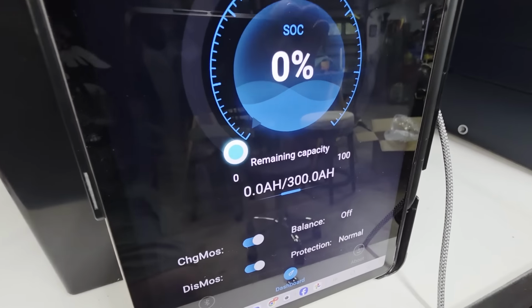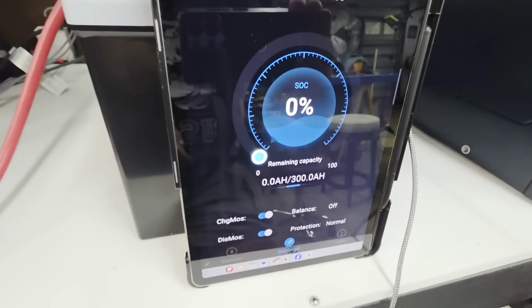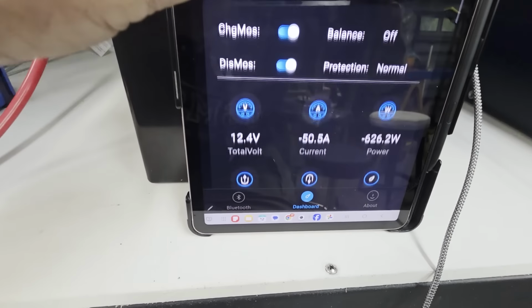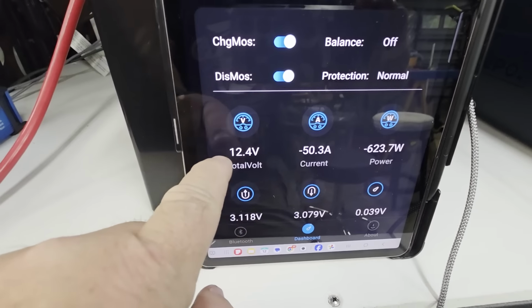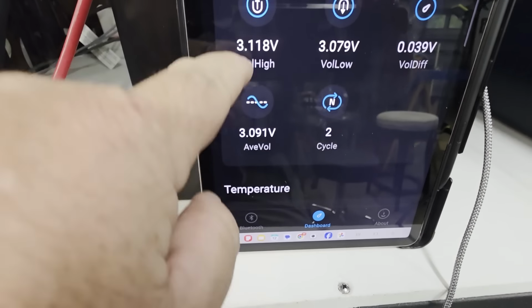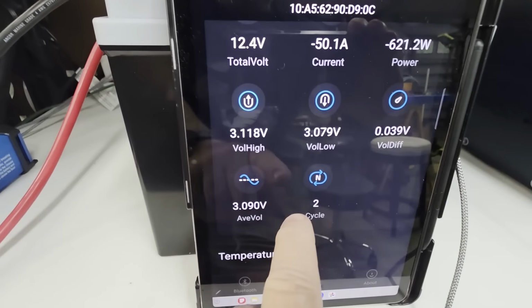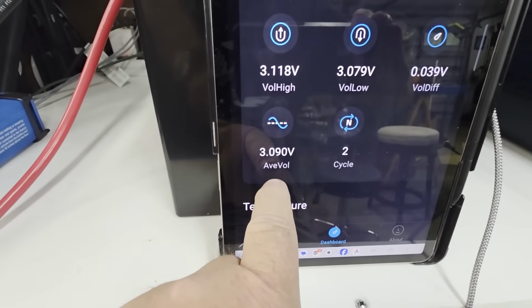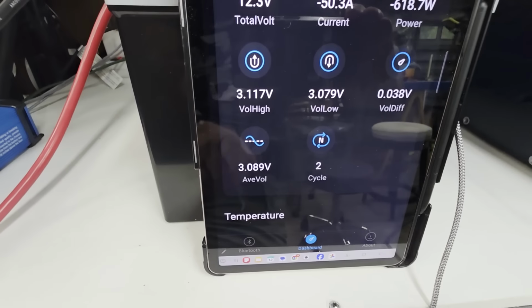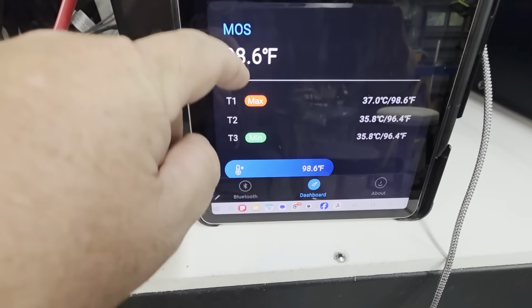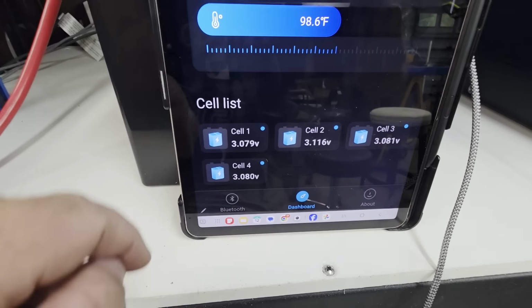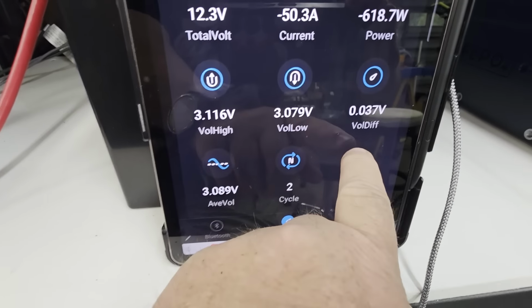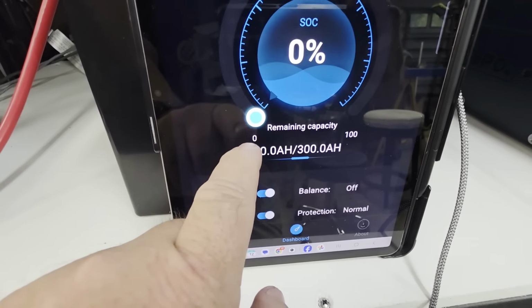Okay, still going, says 0 SOC, 0 amp hours remaining, still discharging 50 amps. Total voltage is 12.4, the cell voltage average is still above 3, so we still have a little ways to go. Let's take a look at all the cells, they're just fine. The differential's starting to grow because we're getting close to the lower knee.